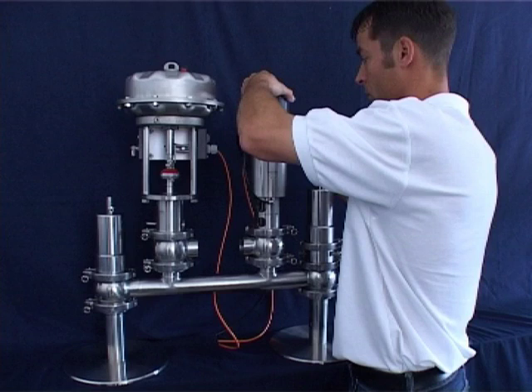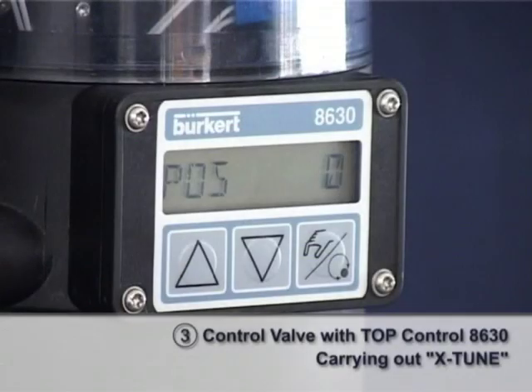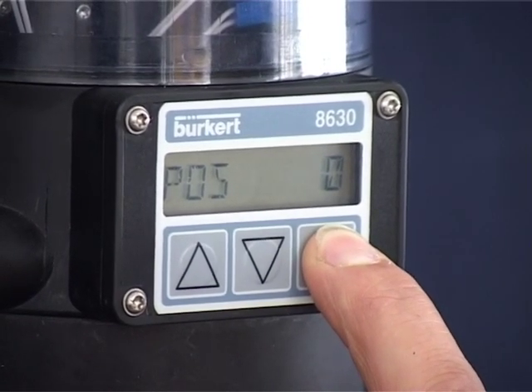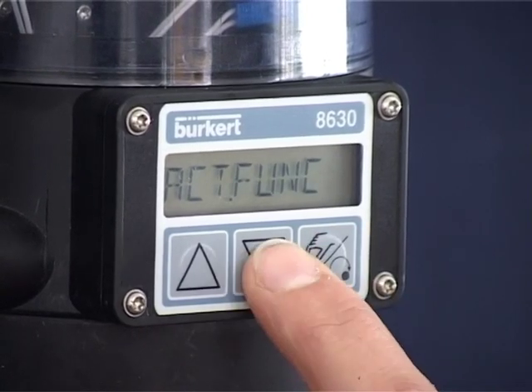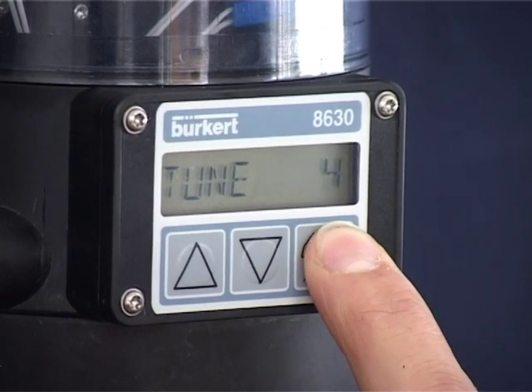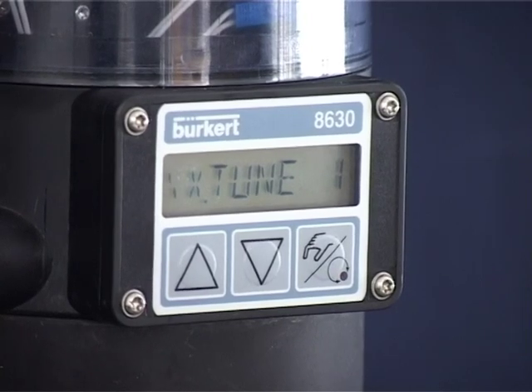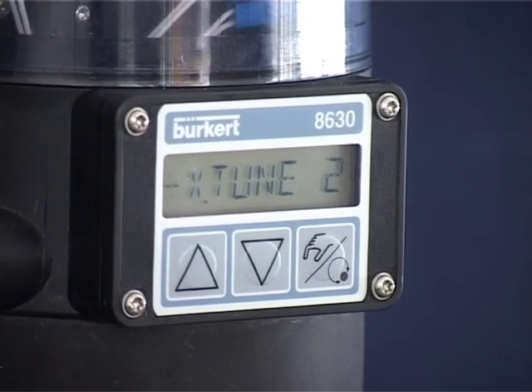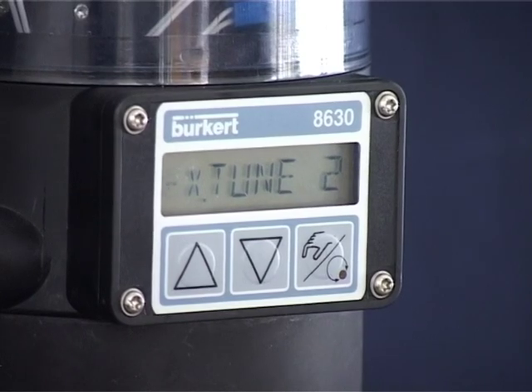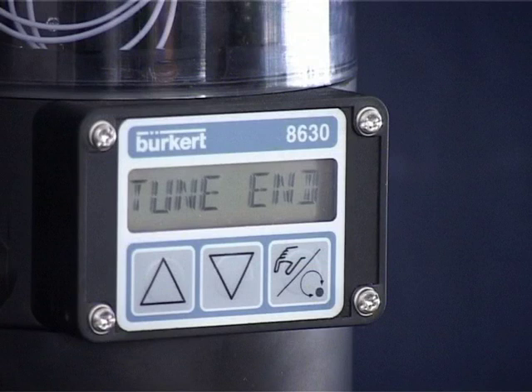Please ensure that the TopControl 8630 is again set to automatic mode. Press the right-hand button for five seconds until ActFunc appears in the display. You can get to the X-Tune display by pressing the middle button several times. Then press the right-hand button for another five seconds and the auto-tune process runs automatically, going through several X-Tune phases. This may take three to eight minutes, depending upon the design.